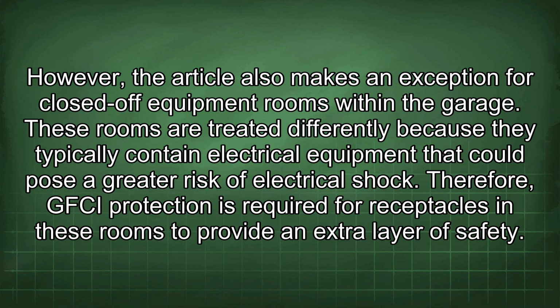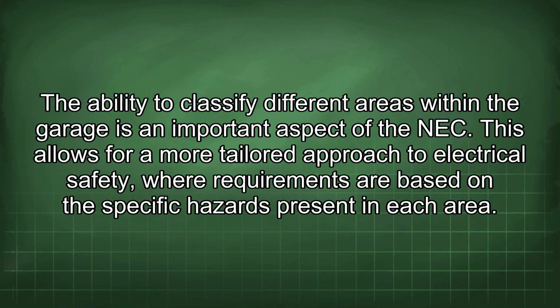These rooms are treated differently because they typically contain electrical equipment that could pose a greater risk of electrical shock. Therefore, GFCI protection is required for receptacles in these rooms to provide an extra layer of safety. The ability to classify different areas within the garage is an important aspect of the NEC.